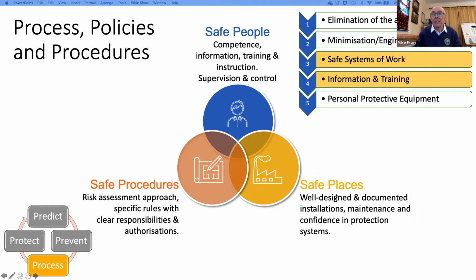As far as arc flash is concerned, safe places means well-designed and documented installations, maintenance, operation I suppose as well, but have confidence in the protection. Is the protection system going to operate? Because if we are going to calculate incident energy on the basis of an upstream device actually operating, I think we really need to have confidence that it is going to operate within the time that we've set. And then finally, safe procedures: having a risk assessment process, specific rules with clear responsibilities, and people that are authorised to carry out that particular work.